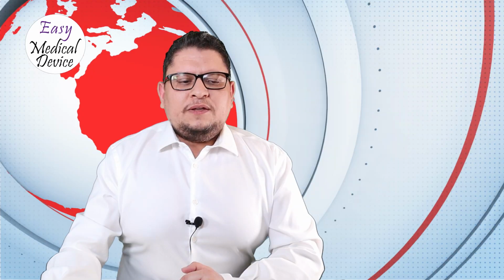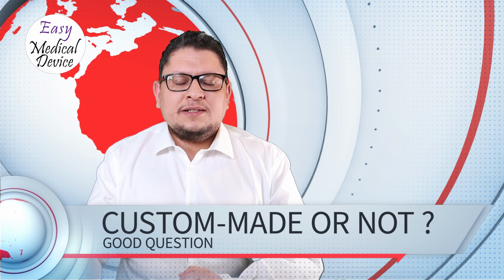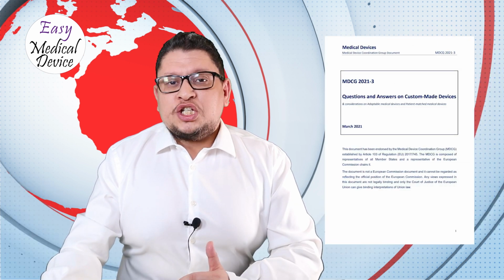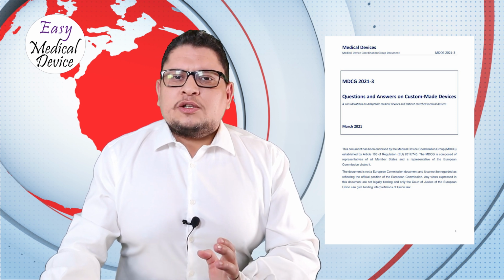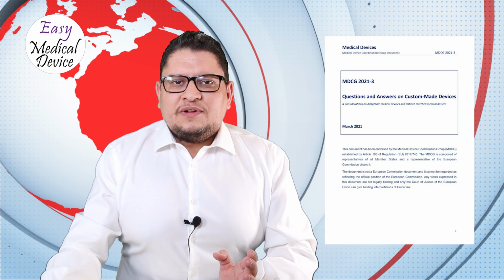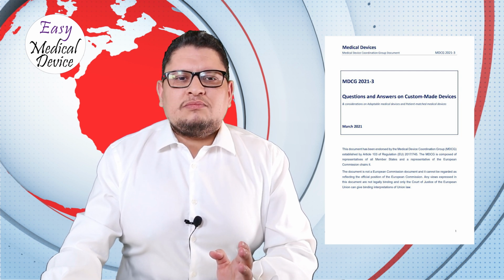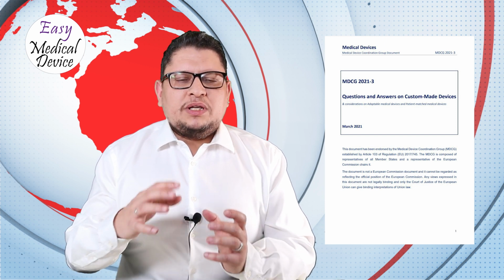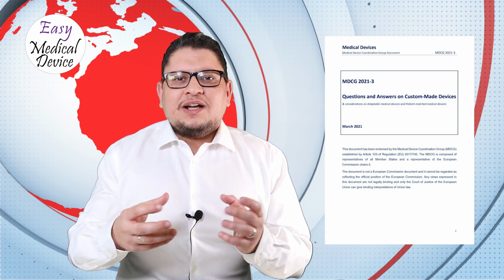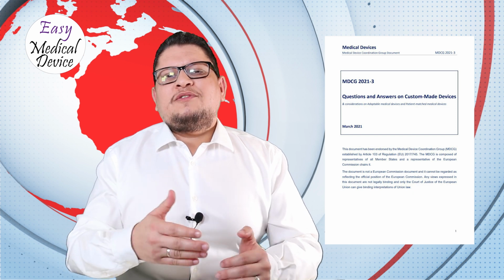So go on the show notes and you will also see this MDCG guidance with all the information that we will talk about today. If you are manufacturing custom-made devices, then the EU Commission's MDCG group issued the MDCG 2021-3, which is questions and answers about custom-made devices. I think it's a good document because it clarifies a lot of things between a custom-made device, an adaptable medical device, or a patient-matched device. Even me, when we are looking at some device, we are asking, is this really a custom-made, or is it just an adaptable device, or just a matching device, where by chance you match the right person for that. So this provides some examples of what a real custom-made device is, what an adaptable device is, and what a patient-matched device is. And it's also providing information about class 3 implantables.